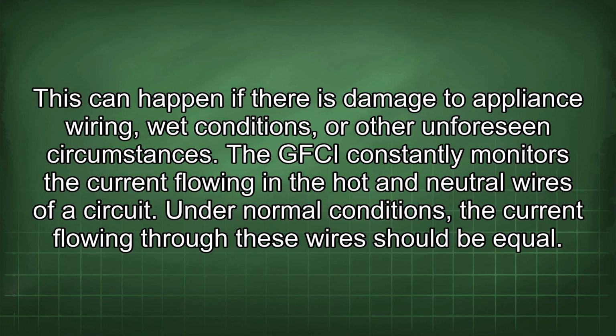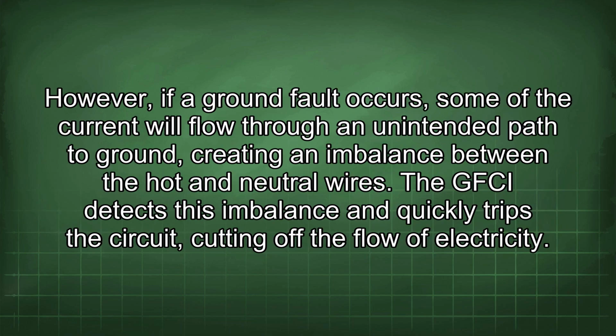This can happen if there is damage to appliance wiring, wet conditions, or other unforeseen circumstances. The GFCI constantly monitors the current flowing in the hot and neutral wires of a circuit. Under normal conditions, the current flowing through these wires should be equal. However, if a ground fault occurs, some of the current will flow through an unintended path to ground, creating an imbalance between the hot and neutral wires. The GFCI detects this imbalance and quickly trips the circuit, cutting off the flow of electricity.